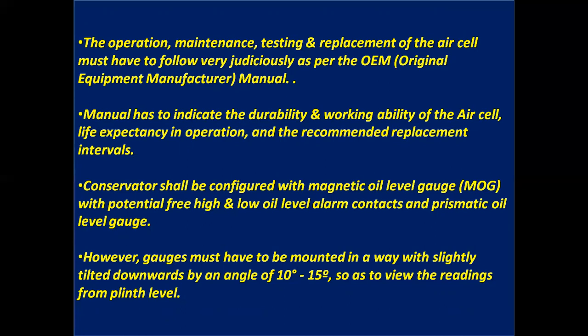However, gauges must have to be monitored and mounted in such a way with slightly tilted downwards by an angle of 10 degree to 15 degree so as to view the ratings and readings of the conservator tank from plinth level. Again, I repeat, gauges must have to be mounted in a way with slightly tilted downwards by an angle of 10 degree to 15 degree so as to view the readings from plinth level.